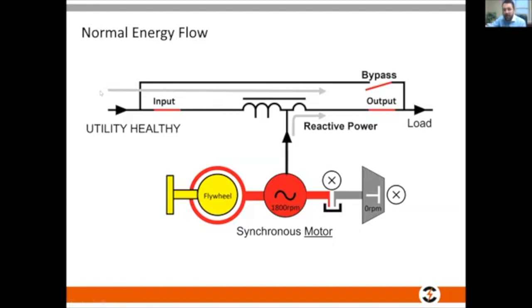As active power comes in, it has poor power quality potentially. It flows across my inductor, which is very low reactance, connected to my alternator, which is very low impedance. The combination of those two allows me to provide a perfect sine wave, superior load handling, free of harmonics, free of power sags, surges, whatever the transients might be. You're going to get this very nice, clean sine wave. I'm providing reactive power because my synchronous motor is spinning.